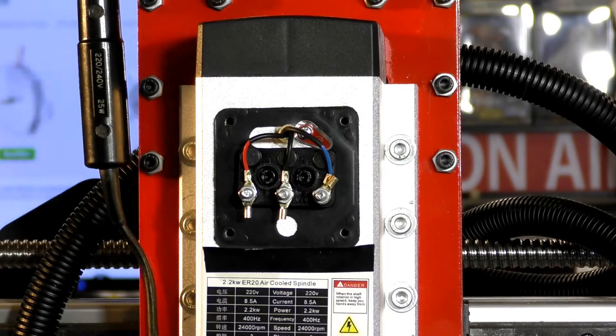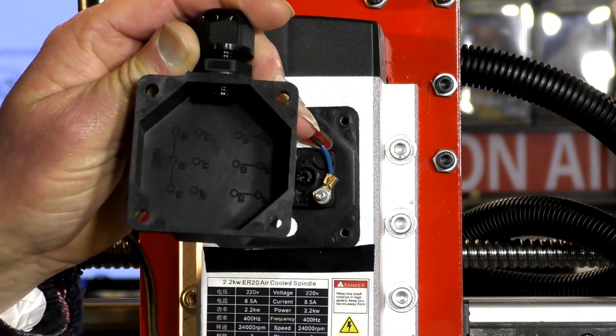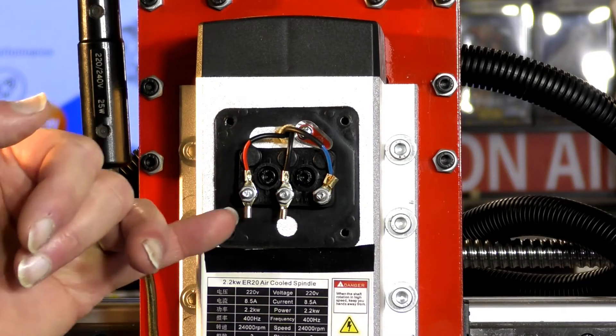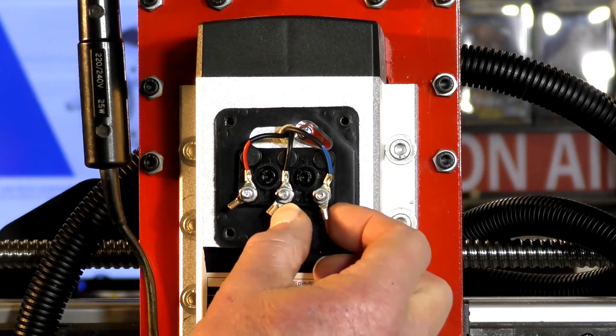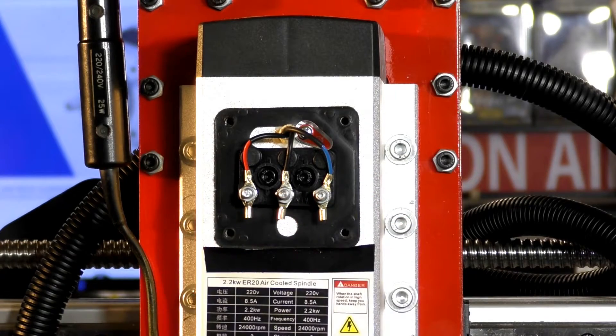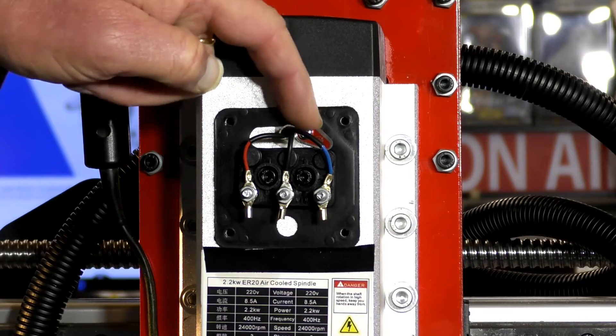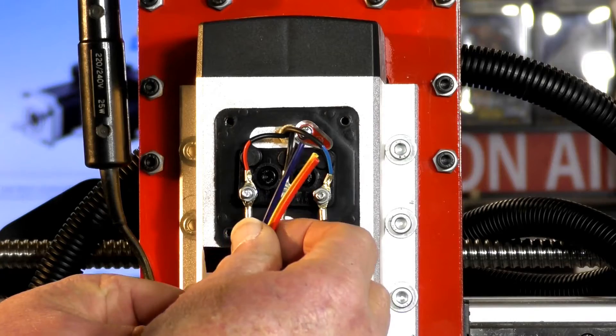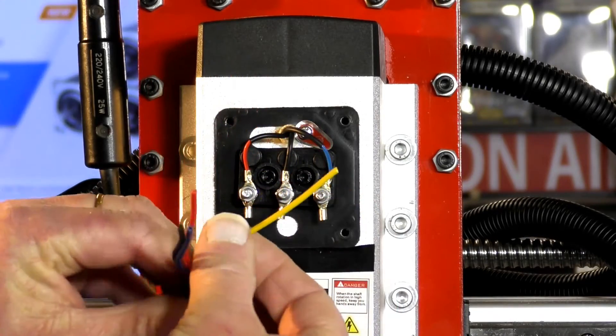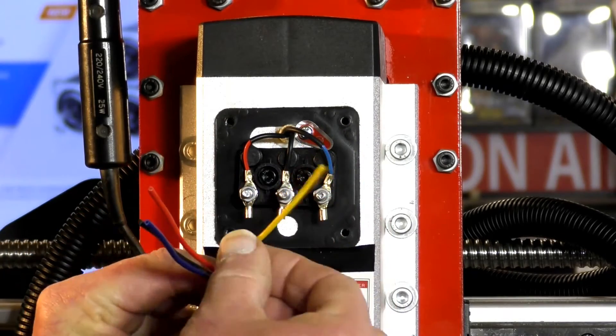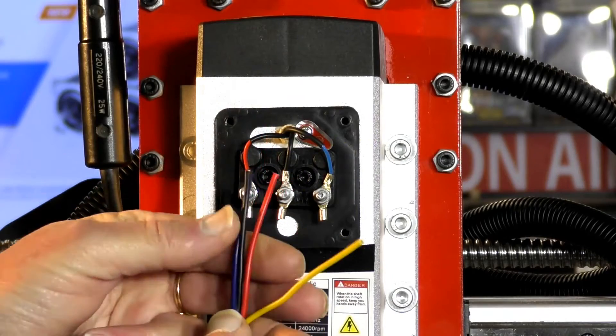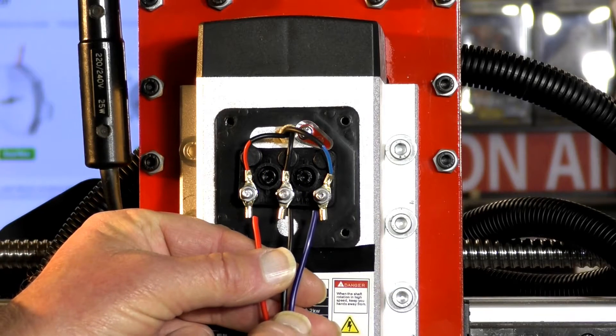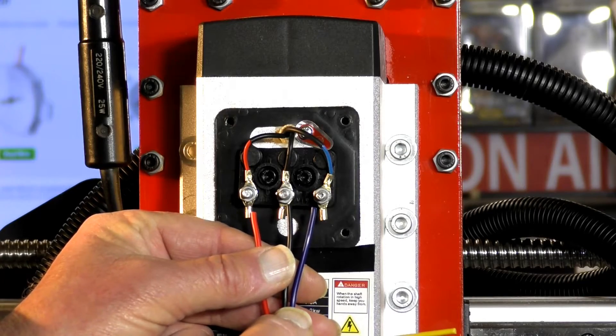You don't rely on crimped electrical connectors for a three-phase unit. I've peeled back the outer layer of insulation on this three-phase four core cabling for the VFD. I won't reveal the wires yet on the end because you've got to get them through the top, and sometimes it can make it awkward. So we're going to take this cover off now. That's what's inside. There's a little wiring diagram printed on the inside telling you how these are connected up.